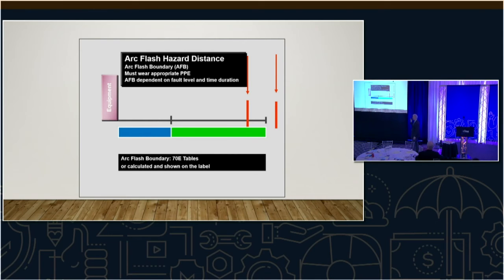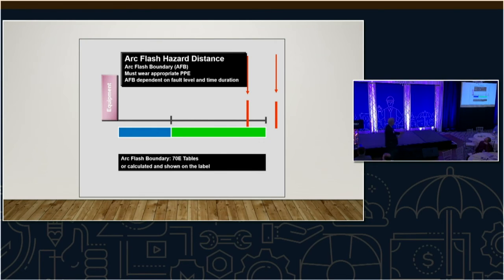And so here's that same table, but now with the arc flash boundary superimposed, but you don't know what it is. It could be inside or it could be outside that other boundary. So you can have a shock boundary that you have to wear PPE in. Okay, fine, the blue, but then the green is, all right, I'm keeping people out this far. Well, what if the arc flash boundary is way out here?